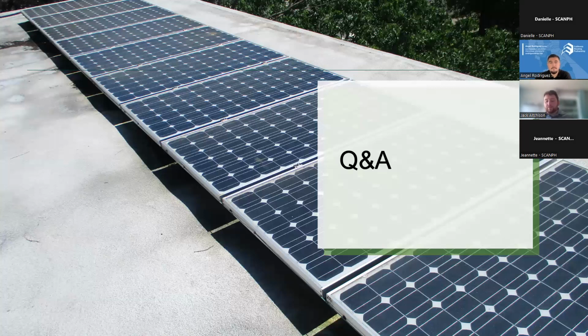Our standard when we're retrofitting heat pump water heaters in existing buildings is to test for crossover before, and sometimes we even monitor to understand how much of the load is recirculation and how much of the load is just supplying hot water to the tenants. In some of these old buildings, people weren't thinking about efficiency when they were retrofitting, and you can see recirc loads of 70% of your water heating load just from recirculating water. That's due to crossover, and also to imbalance issues and uninsulated piping. With the gas water heater, you're able to cover that load. The heat pump water heater can be affected more because of that limited recovery. It's not as resilient to inflated load issues.